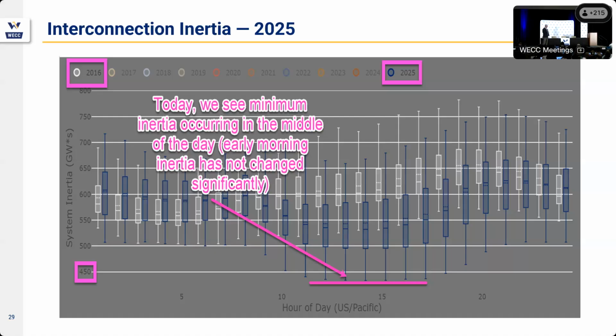If you wanted to really control frequency to 60 cycles at all times, you'd burn a lot of fuel to do it. So as an industry, we said we can let frequency move. Generally, the deadband is about 40 millihertz, plus or minus. So we allow that frequency to move between 59.96 and 60.04 without any governor control action. And we do that to save fuel, save wear and tear, save a lot of things on a generator.